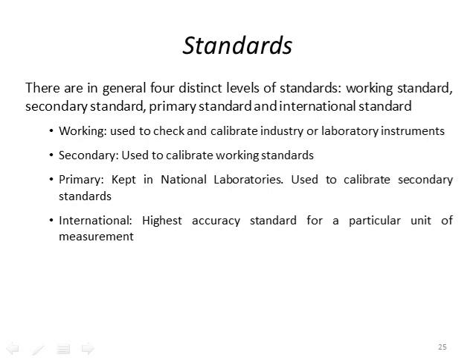The international standard is the highest accuracy standard for a particular unit of measure. Primary standards are kept in national laboratories and used to calibrate secondary standards. Secondary standards are used to calibrate working standards, which should be in all laboratories. If you have an oscilloscope or digital voltmeter, there should be a standard in the laboratory that allows you to check whether the instrument needs calibration — to see if some offset has developed over time. We will expand on these in more detail over the next approximately 20 slides.